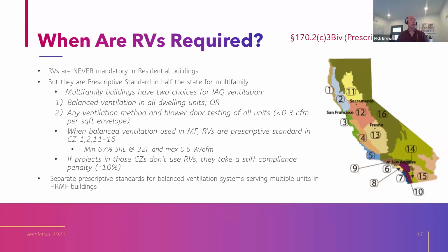So when is a recovery ventilator required? Well, they're never mandatory, but they are prescriptive standard in roughly half the state for multifamily. Multifamily buildings under the current 2022 code have two choices for indoor air quality ventilation. And I've reproduced the climate zone map on the right for you to get calibrated on which climate zones. But you can do balanced ventilation in all dwelling units or any ventilation method and blower door testing of the units. They need to come in under 0.3 CFM per square foot of envelope. Now, when balanced ventilation is used in multifamily, recovery ventilators are prescriptive standard in climate zones 1, 2, and 11 through 16.